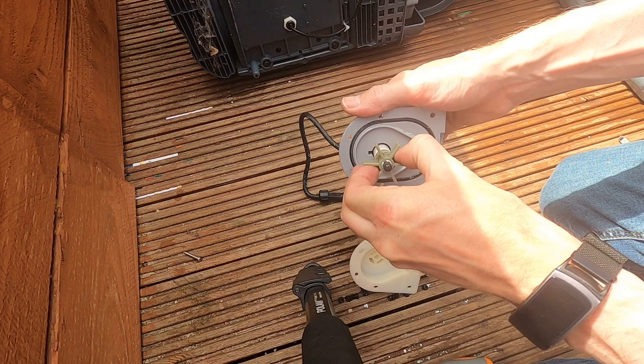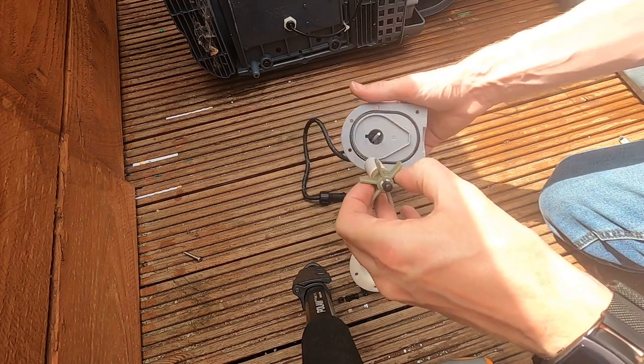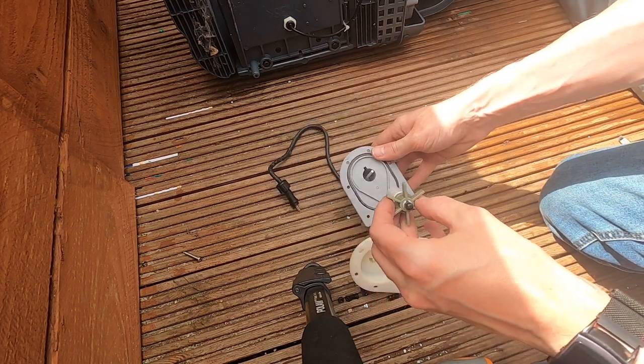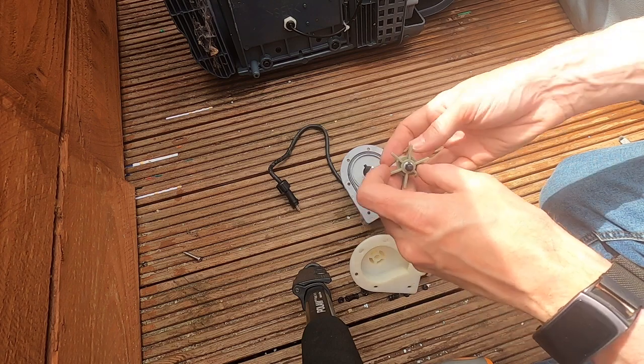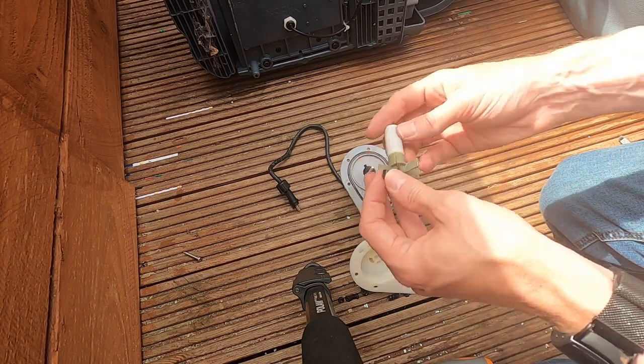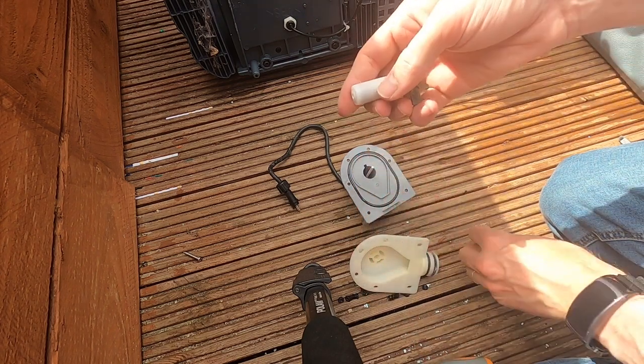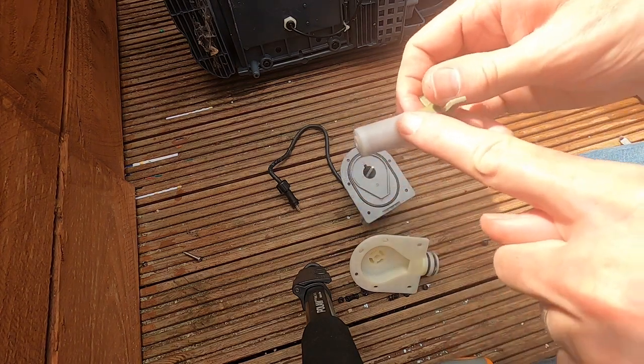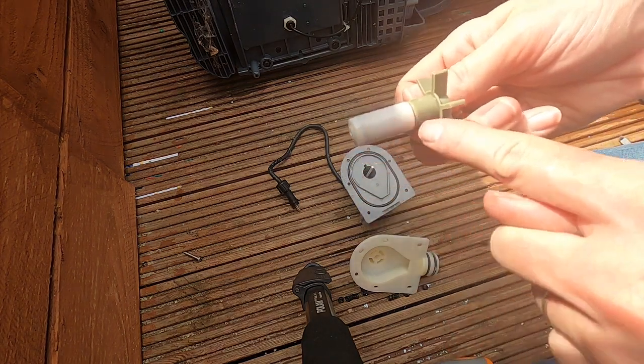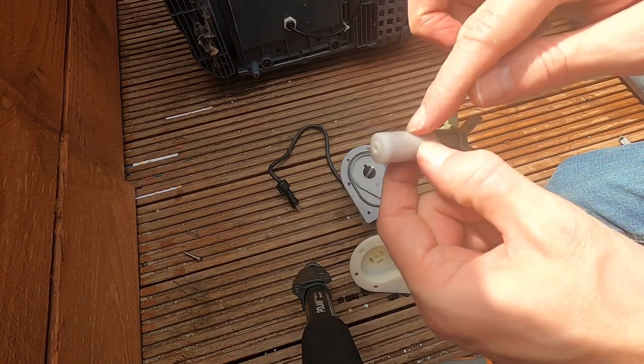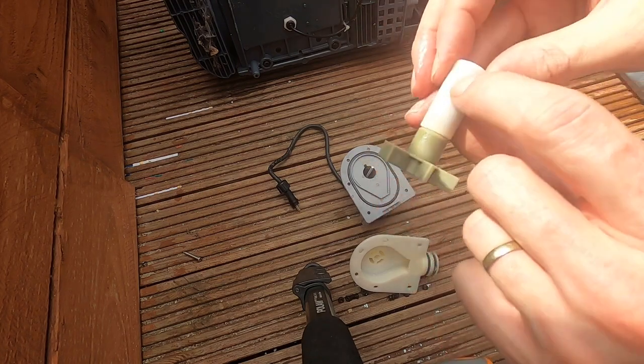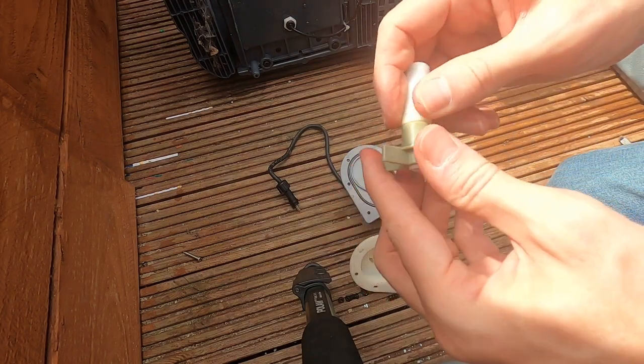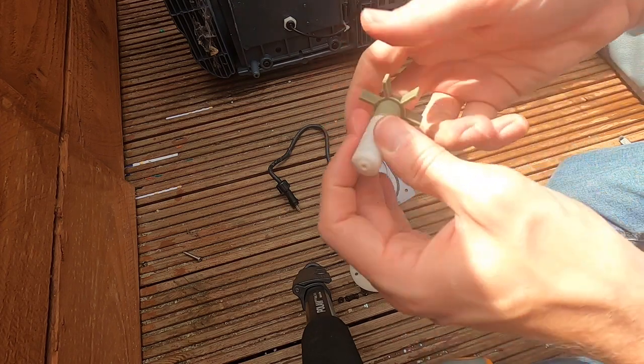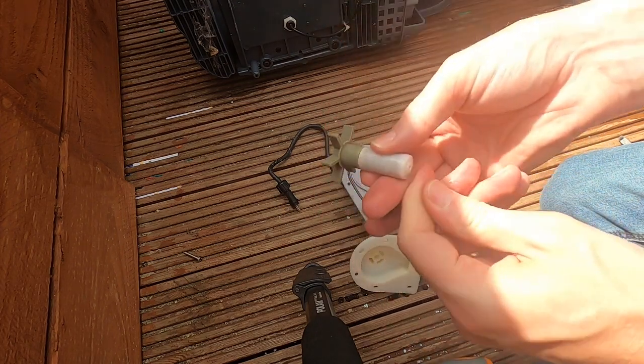And then you can lift the impeller out. You can see in this case the stick has stayed in the bottom, so be careful you don't lose the little cap end. What you're checking for here is whether this plastic is damaged in any way. What happens is this plastic cracks and inside is the magnet, and it will then corrode and damage. Now you can see this is in really quite good condition.